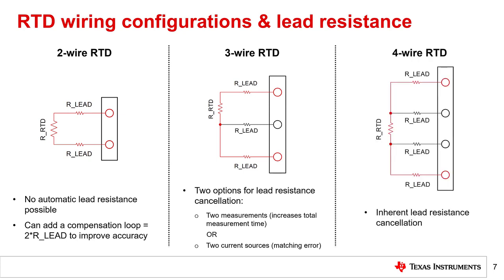The final RTD wiring option is a four-wire RTD. Like two and three-wire RTDs, each wire in a four-wire RTD has some lead resistance. However, the bias current only passes through R lead in the top and bottom legs, which enables direct measurement of the RTD resistance without any influence from R lead. In other words, a four-wire RTD provides inherent lead wire resistance cancellation. Subsequent Precision Labs modules expand upon the basic circuit analysis and cover topics including how to measure each RTD type, measuring multiple RTDs, measurement system errors, calibration, selecting components for design, and RTD wire break detection.